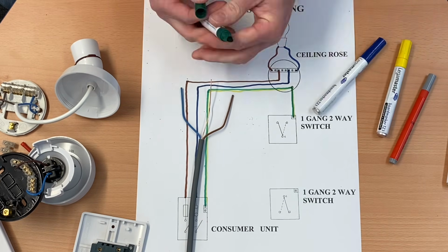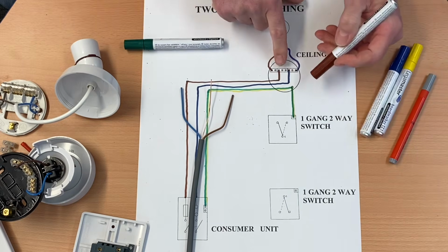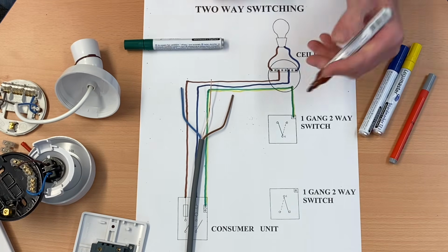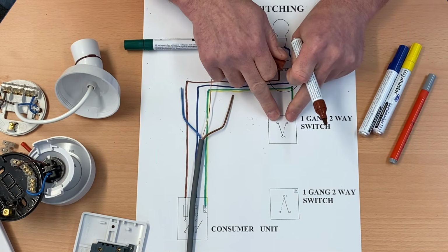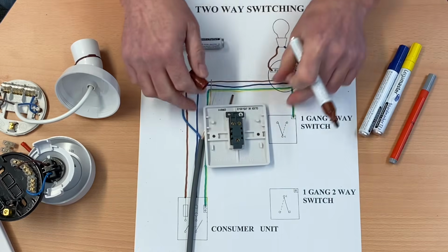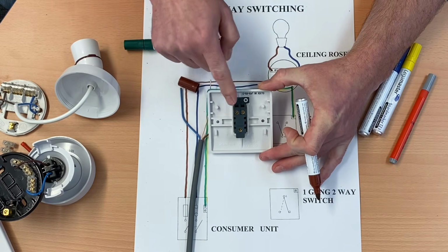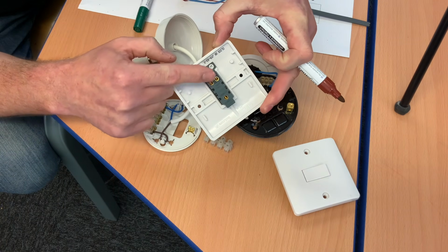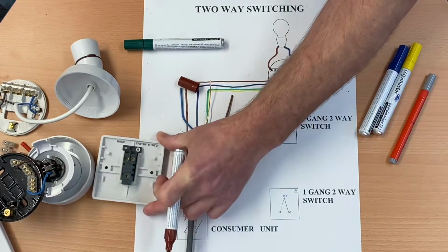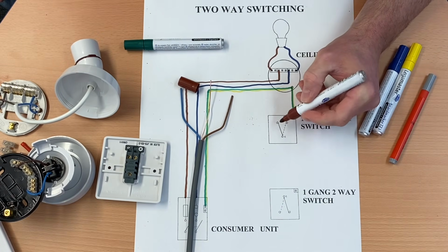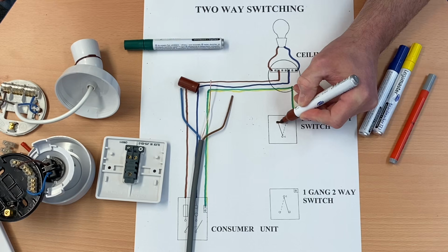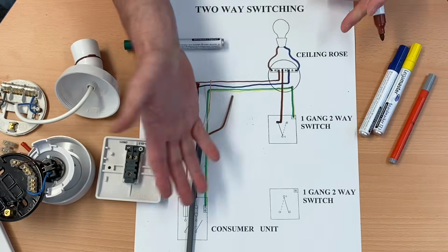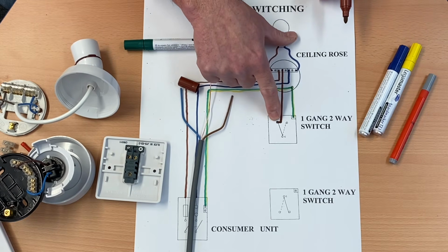We're going to bring down our permanent line connection. So the permanent line coming out of the loop, there's 2 terminals left. It doesn't matter which one I choose, but I'm going to bring down my permanent line connection. And it doesn't matter whether it goes in L1 or L2. So as we look at our switch, we've got common on its own and L1 and L2. It doesn't matter which one of those 2 it goes in, as long as it doesn't go into common. So for ease of my drawing, I'm just going to bring this cable out a little bit that way and just bring that line up into the loop. So I've taken one down into L1 or L2. So that would be my permanent line coming down.